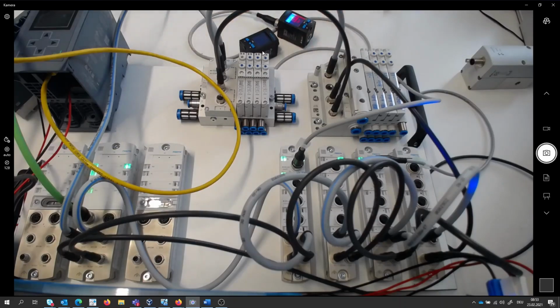That means for us, to sum up, first of all, we can change parameters during operation with the corresponding function block of Festo. If we want to use the validation, we have to activate the parameter inside the IO link master. If we want to use the backup functionality, then we have to activate it also in the IO link master. But additionally, after changing the parameters, we have to execute one time the system command from the IO link specification so that the master is creating a backup of the connected IO link device and the corresponding parameters that we have changed.